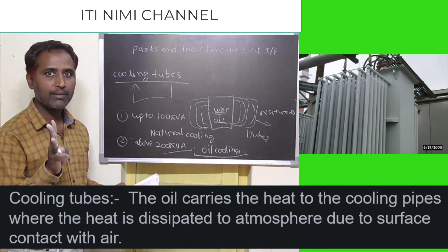Let us see the next one, tap changing transformer. But first, a small point: the transformer oil - various types of transformer oils are available in the market. I will tell you three names. First is mineral oil, the insulating oil put inside the transformer core to carry the heat. Second is silicone liquid. Third is hydrocarbon liquid. These three types of oils are used in the transformer.